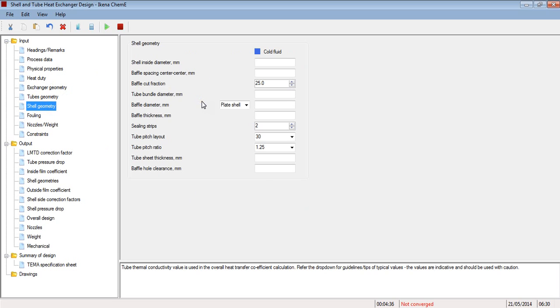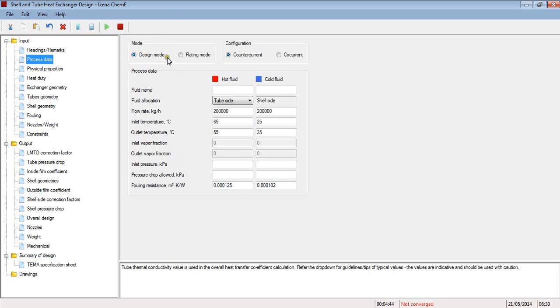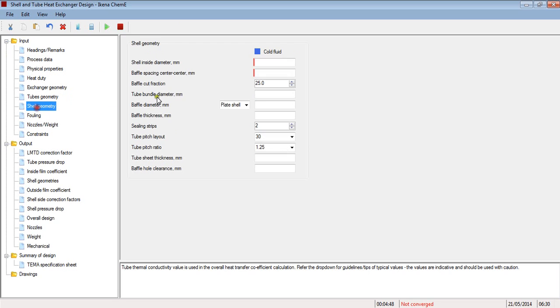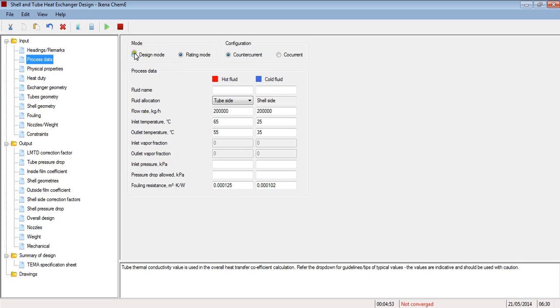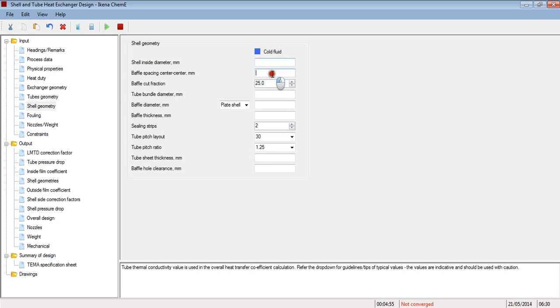Shell side input can be entered here. Since we are running in design mode, we don't really need to enter all of these values. We can leave them blank. As you can see, we are running design mode, but if you choose to run the rating mode, you will have to enter the value of these 2, but I will go ahead and use design mode. Okay, and if you decide to enter a value here, I will go ahead and use a value for baffle spacing. I will specify a value. The program will honor that, but if you don't, the program will calculate it for you.